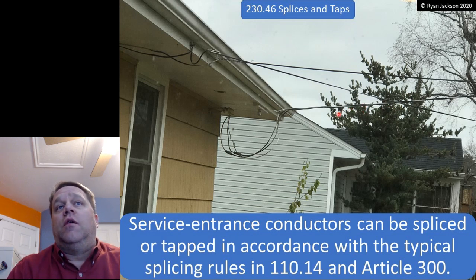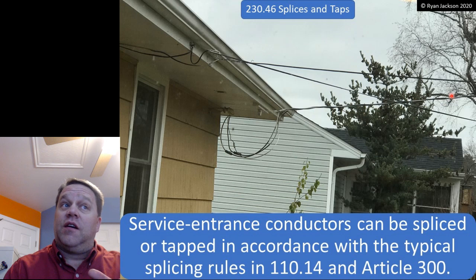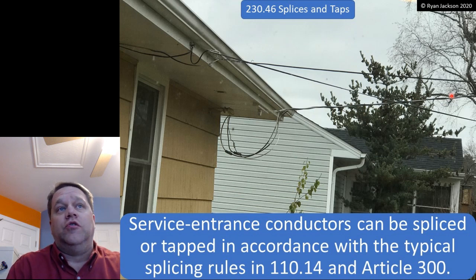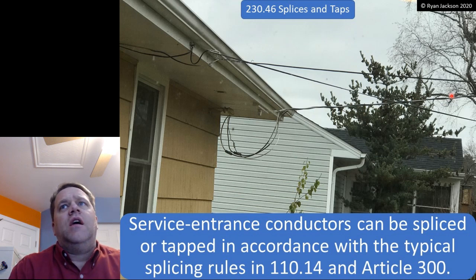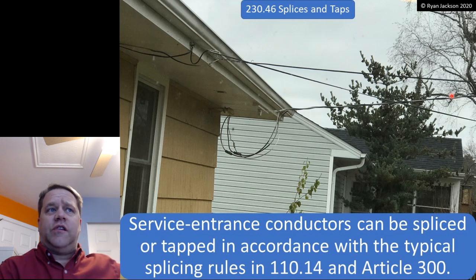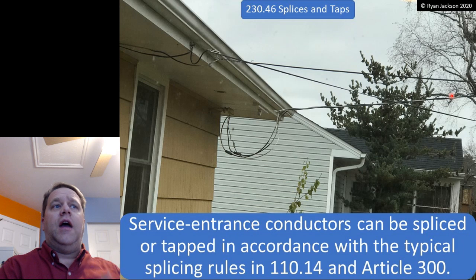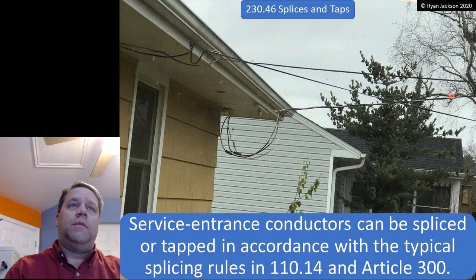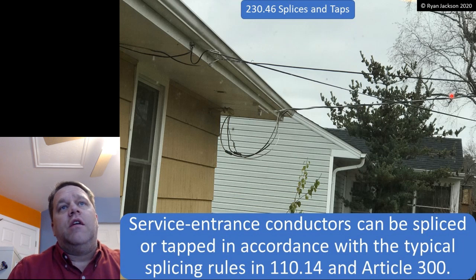If this was, I don't want to say a customer-owned transformer, that would be pretty unusual for residential. But if the utility decided that they were going to stop out at the transformer and you were responsible from the transformer to the house, if that was the case, then these overhead conductors are service conductors and they're regulated by the NEC.